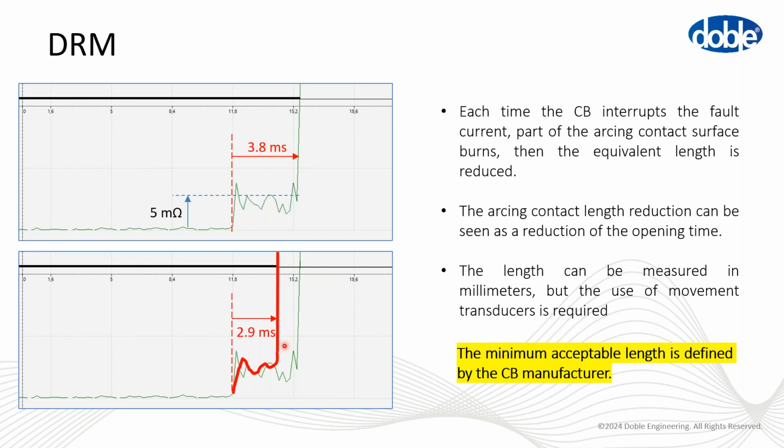Actually, the duration is not a good way to evaluate this. In fact, you should evaluate the length, so in millimeters, not in milliseconds. You can do this by using a travel transducer together with this test.